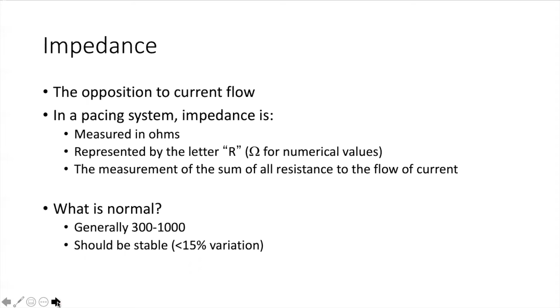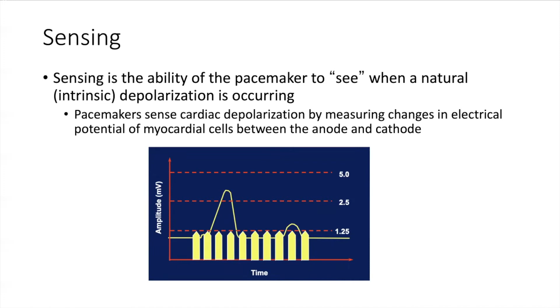And finally, sensing. Sensing is the ability of the pacemaker to see when a natural intrinsic depolarization is occurring. It's sort of like a fence. If we set the sensing to a particular level fence, if the intrinsic beat is lower than that, then the pacemaker won't see it. And if it's higher than that, then the pacemaker will detect that impulse. And you can see in this example, the sensitivity setting, this fence here, is set such that the pacemaker will likely sense this intrinsic QRS, but also likely oversense this T wave.